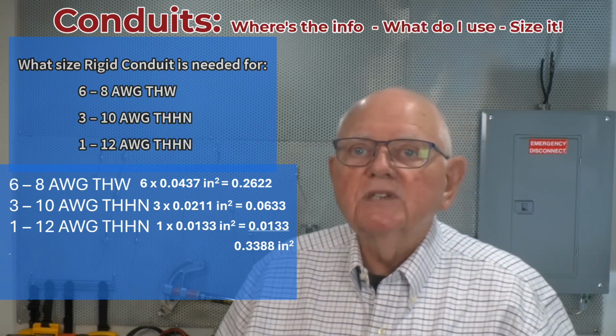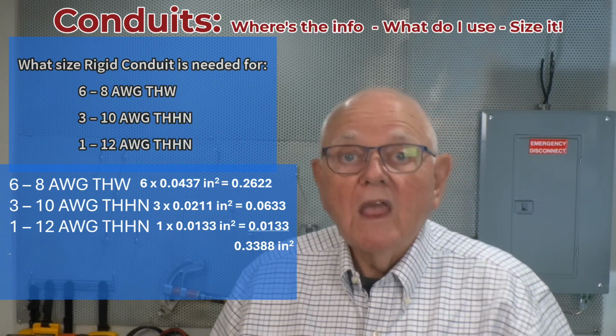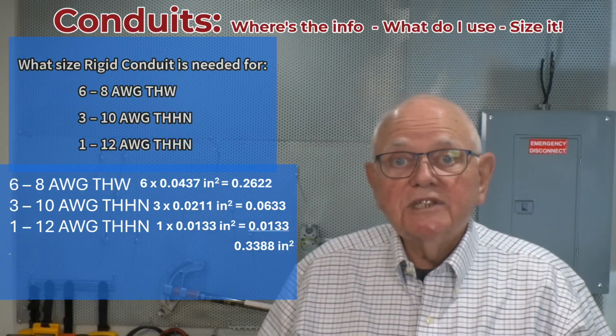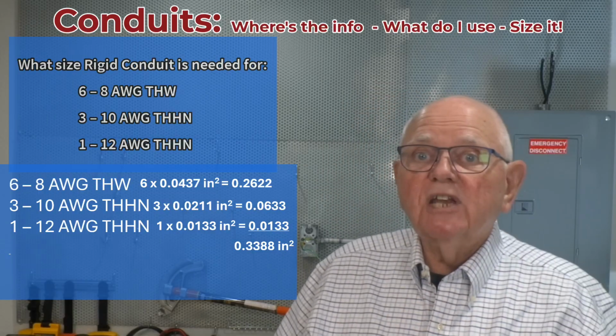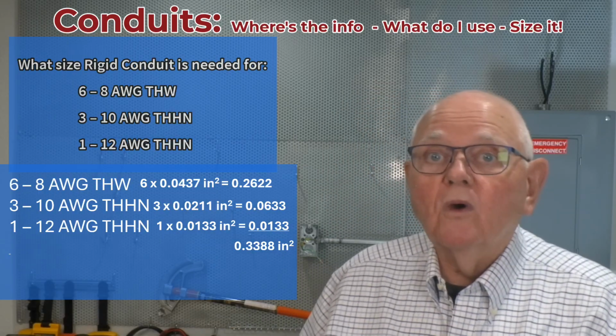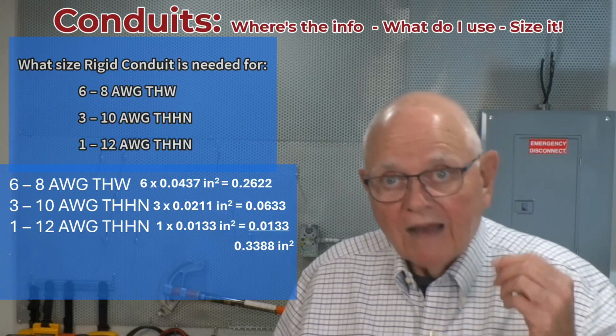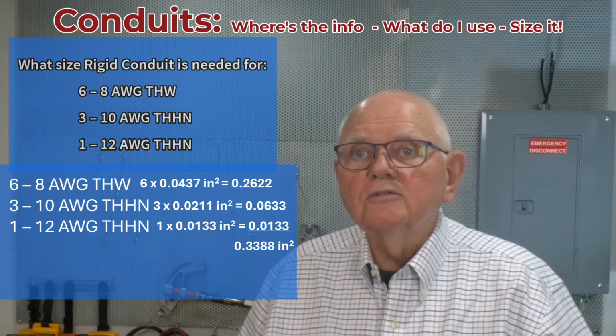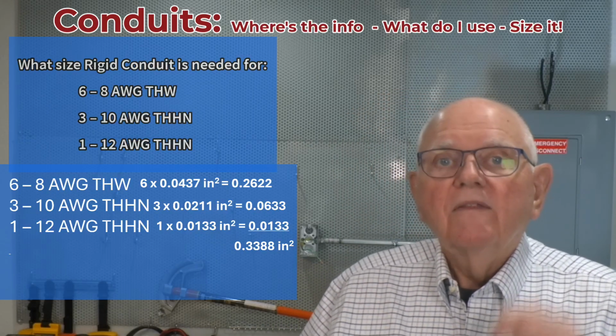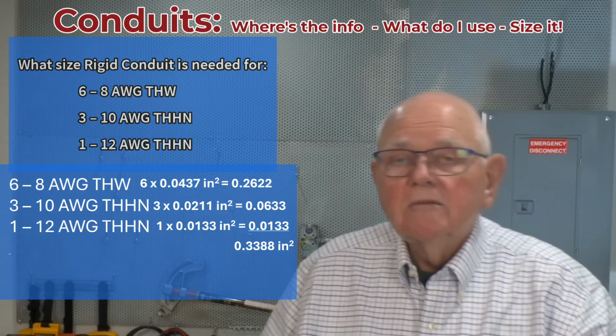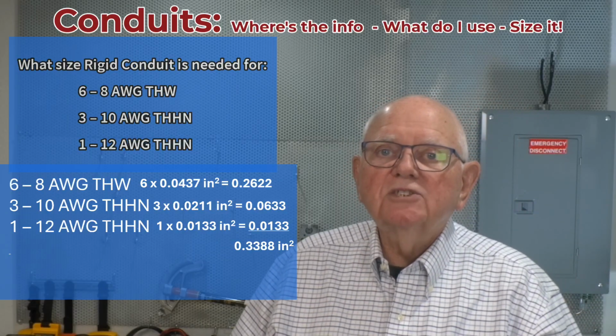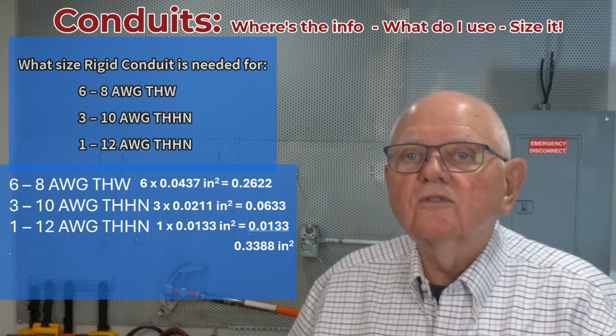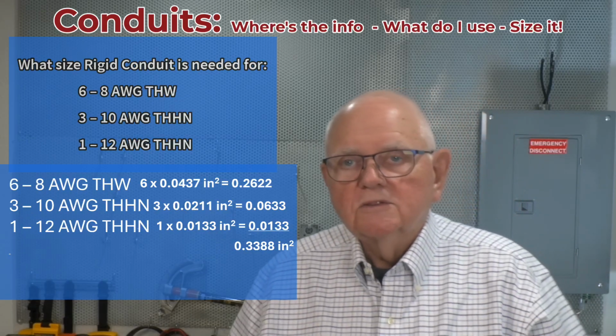You can see the numbers, 0.2622. I've got 3 number 10s THHN. Each THHN is 0.0211 according to table 5. I've got 3 of them for a total of 0.0633. Then I only have 1 number 12. I looked that up, and number 12 THHN is 0.0133 square inches.